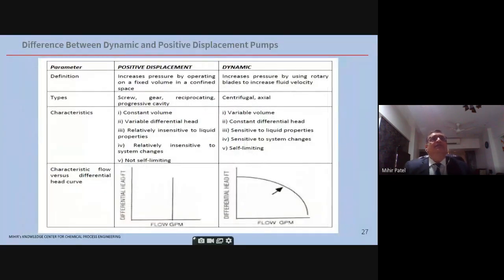Now we'll cover the difference between dynamic and positive displacement pumps. So here you can see the first column is positive displacement. So screw pump, gear pump, reciprocating, progressive cavity, these are positive displacement pumps. They are constant volume and basically they operate on the back pressure principle. So the more the back pressure, again they will push more and more, unlike a centrifugal pump. As you can see, the characteristic curve has a single flow straight line and the differential head can be anything. It depends on the back pressure.